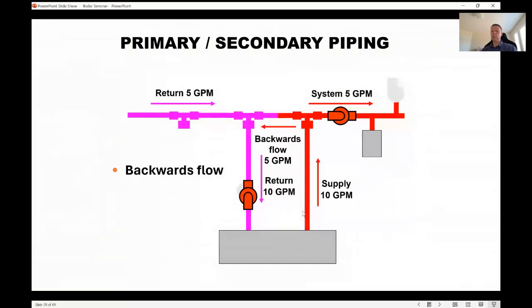Say that building's cold, it's calling, I need heat. Well, the supply temperature set point, let's say it's 180, whatever it is, 160, you might reach that and overshoot it. You're going to shut off because you're recirculating that water. Well, that room's still cold. It's going to draw that down within no time, say, hey, we're below set point, turn on, and that on off, that cycling situation. And one thing you'll find is any gas boiler does not want to cycle. Cycling is probably the hardest thing you can do to it and something you really want to avoid.